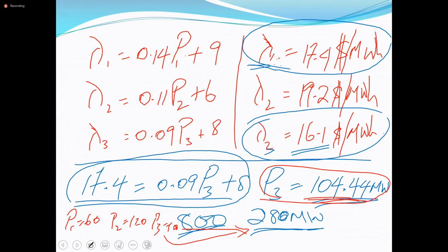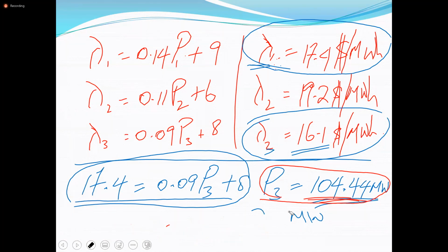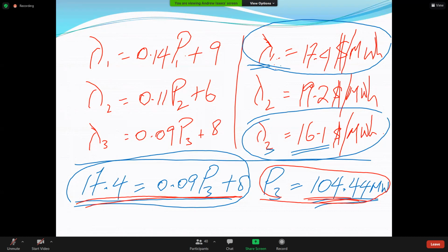Is that clear? Have I confused anybody? I'm trying to explain the reason we conduct this particular test. I'm going back to what Mr. Allen said. He said it was to test whether or not unit 3 would have reached its maximum. I am correcting him by saying you're not testing to see whether unit 3 reaches its maximum. You are testing to see at what point, in terms of output of unit 3, unit 1 would also need to come into the picture.